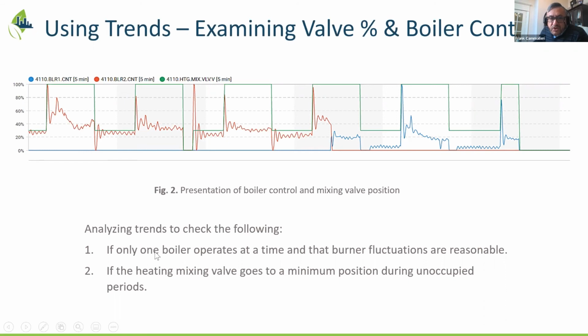In this case, we're investigating trends to make sure that only one boiler operates at a time and that burner fluctuations are reasonable. Here you can see the red line, which is the burner operation of boiler number 2, and over here is boiler number 1. First point is that only one boiler is operating. Boiler 1 is off here, and boiler 2 is running. So that part works, and the fluctuation isn't unreasonable.